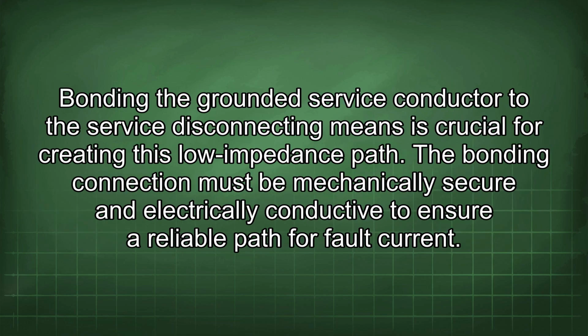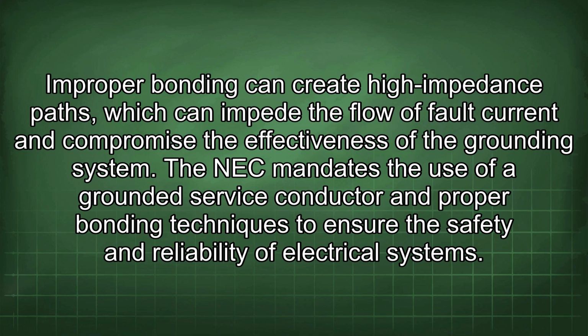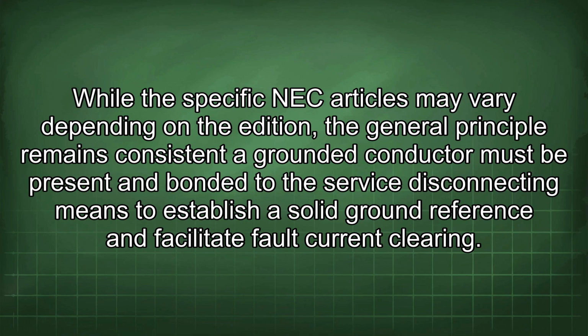Bonding the grounded service conductor to the service disconnecting means is crucial for creating this low impedance path. The bonding connection must be mechanically secure and electrically conductive to ensure a reliable path for fault current. Improper bonding can create high impedance paths, which can impede the flow of fault current and compromise the effectiveness of the grounding system. The NEC mandates the use of a grounded service conductor and proper bonding techniques to ensure the safety and reliability of electrical systems. While the specific NEC articles may vary depending on the edition, the general principle remains consistent.